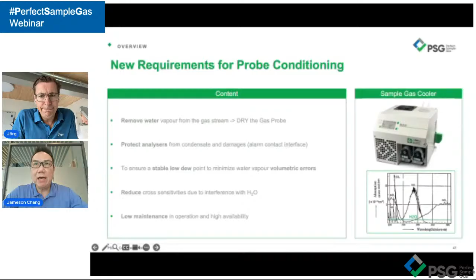For a standard CEMS system, measuring CO2, SO2, NOx, oxygen, a cold dry is the most economical, easiest to maintain, and very easy for the system integrator who is doing it. So therefore, we use a cooler, right? There are gases where you need to measure HCl, HF, NH3, which is ammonia. These are very easily washed out.